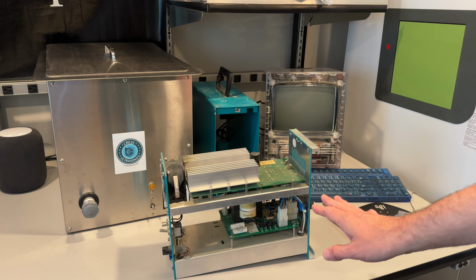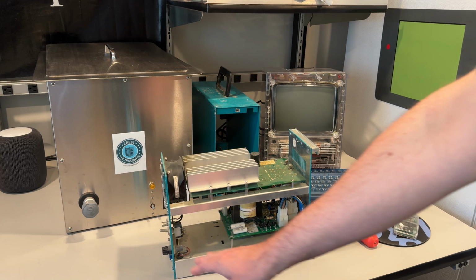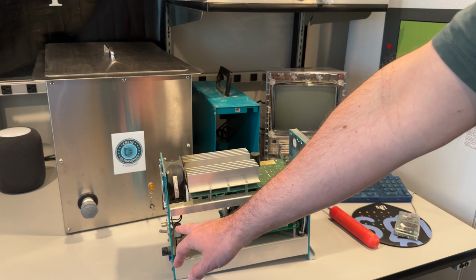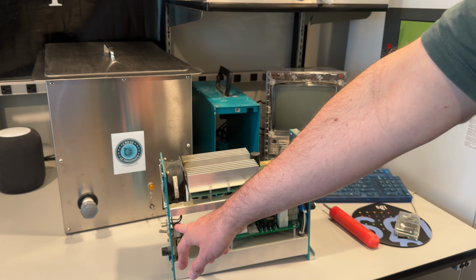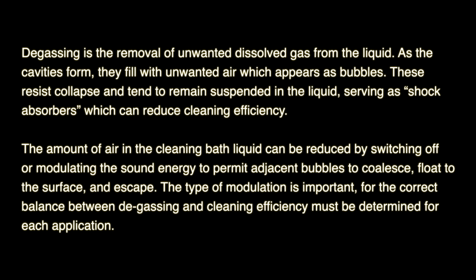And then again, on the inside, it's really straightforward. You have the fuse. This switch is to off gas, so it runs the transducers at a half frequency, I think. And the intent is to off gas the liquid to make the cavitation more effective. The manual gets into that.